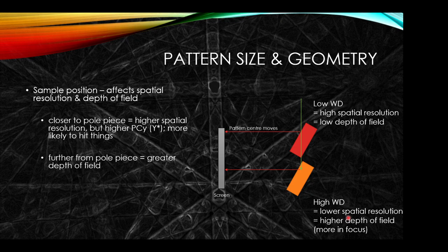Importantly, the pattern center will move down the detector, so you have to be careful about PCY in this case. Also at a low working distance you're more likely to hit things — specifically the very expensive pole piece. Please don't hit the pole piece. It's an expensive thing to fix. So a larger working distance is generally safer, especially for rougher samples.